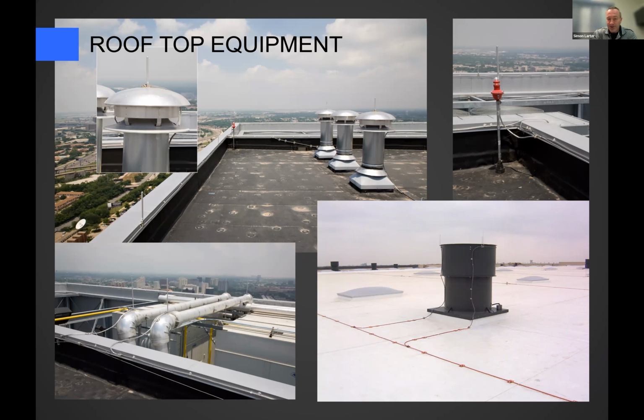If it's a grounded metal body and it's not outside the zone of protection, there's the potential for lightning to look at that grounded body and think, oh, that's a better path to ground than I've got currently. Let me arc over there. The last thing we want is lightning arcing over to another building grounded system. So lightning could possibly do that if there were another path to ground. So to prevent that, we make a bonding connection to a metal body of inductance. That's just a secondary bonding connection to equalize the potential. Where there is no potential, there's no chance of current flow. So the majority of lightning current will stay on our lightning protection system and go safely to ground.